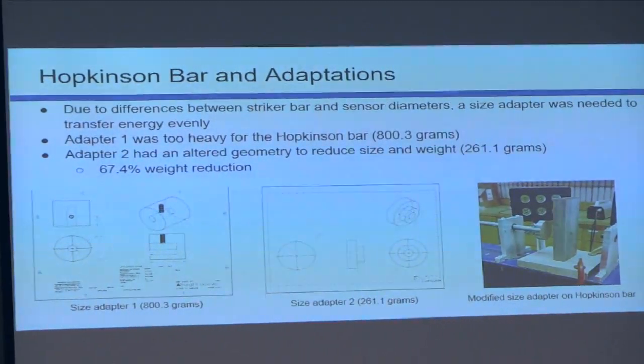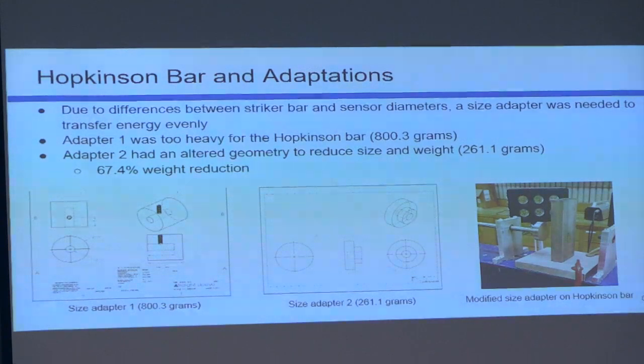So here I'm going to talk about the adapter. The reason why the Hopkinson bar needs an adapter is because the Hopkinson bar itself is 1/2 inch in diameter, while the sensors can range from 1.5 to 2 inches in diameter, roughly. The whole goal of the adapter is to distribute the force more uniformly on the diameter of the sensor, and it also provides a method of mounting the sensor to the backplate. It sandwiches the sensor between the backplate and the adapter, rather than using an adhesive, so that we can swap and run tests quicker.